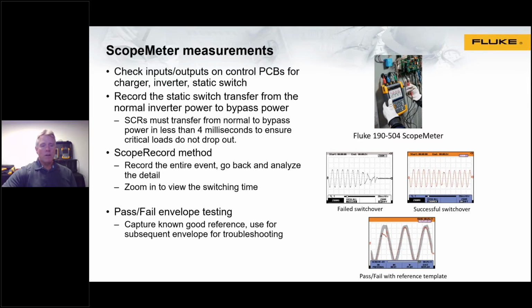Another mode that the scope meters have is if you know what a successful switchover should look like, as is evidenced on the lower waveform, you can actually set up or capture a known good signal, a known good switchover, and then build an envelope, that's what's in the gray, around that for troubleshooting, so that anything that falls outside the envelope could be captured as a failure. And again, the waveforms can then be analyzed or examined. So again, for troubleshooting and maintenance, scope meters are a very versatile tool in a wide variety of applications, but especially for the critical backup system.